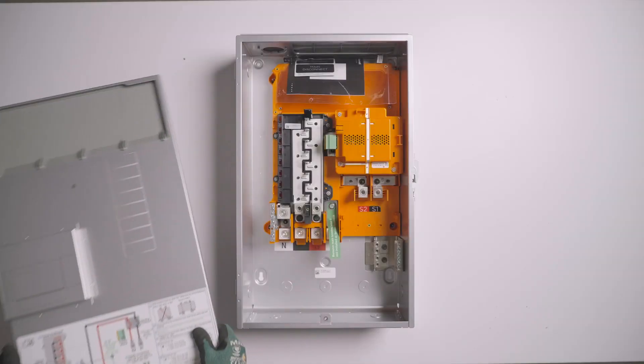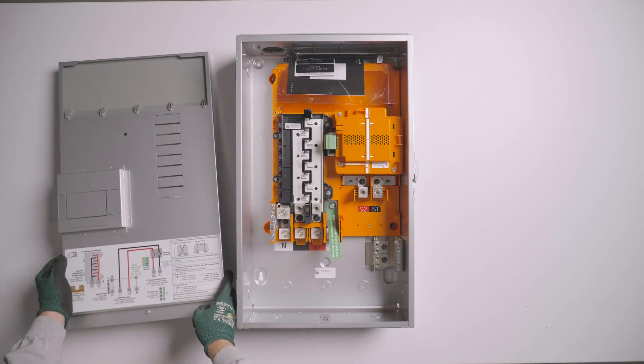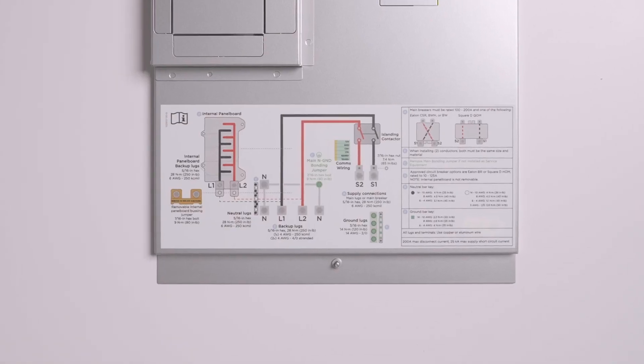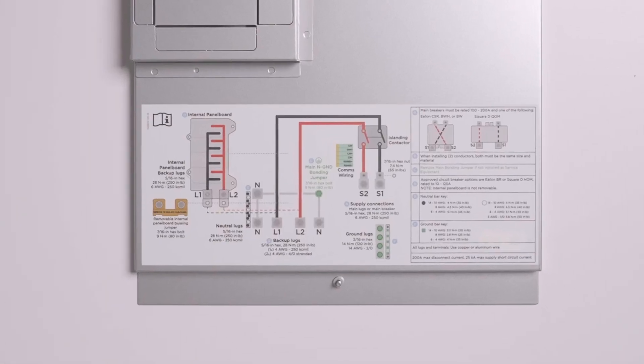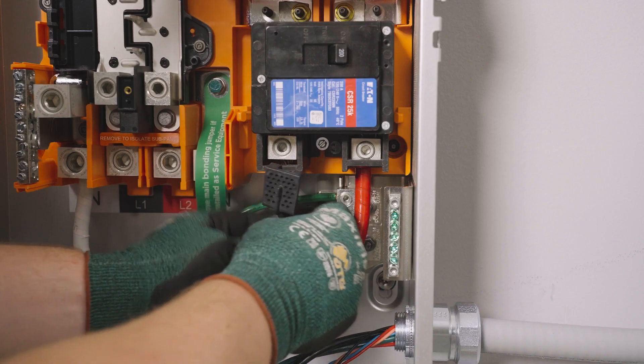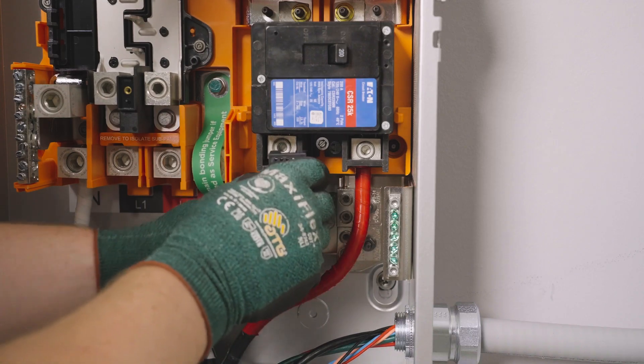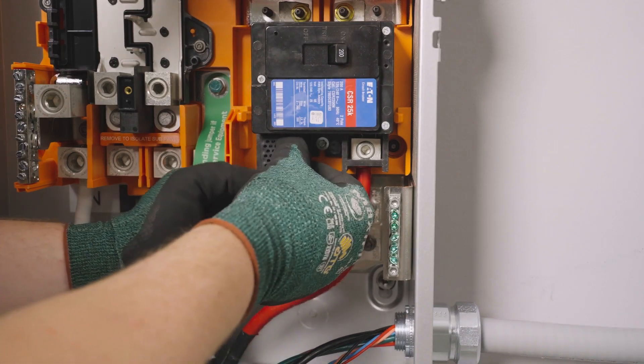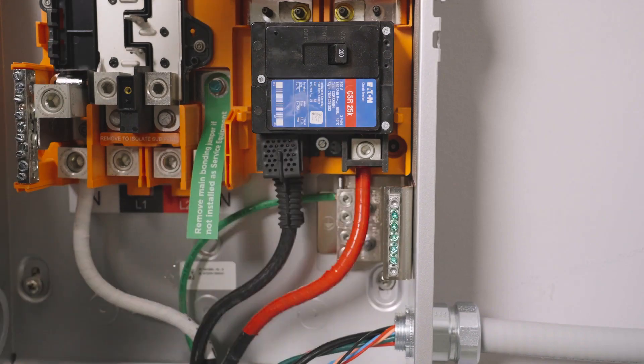This label on the front cover is a valuable field resource as it lists torque specs and allowable wire size of all terminations within the equipment. When required by local code, install the lug covers that were provided with the main breaker.